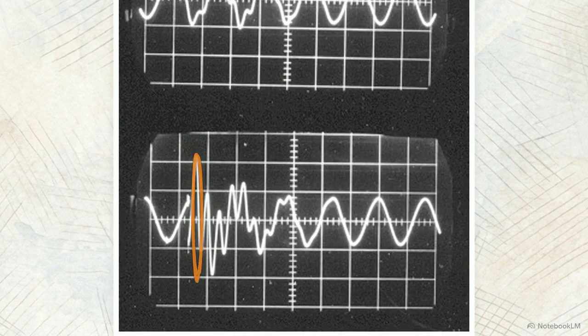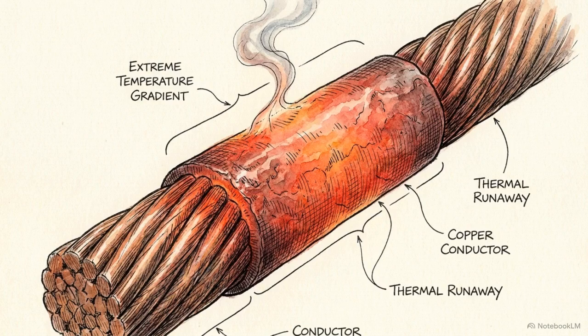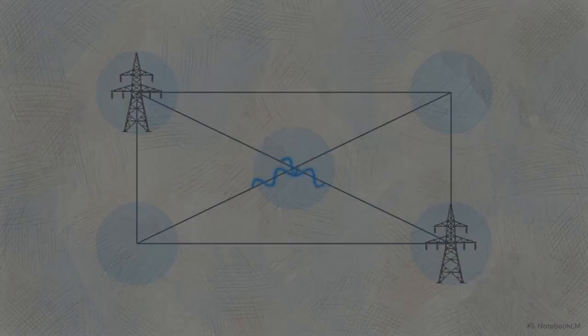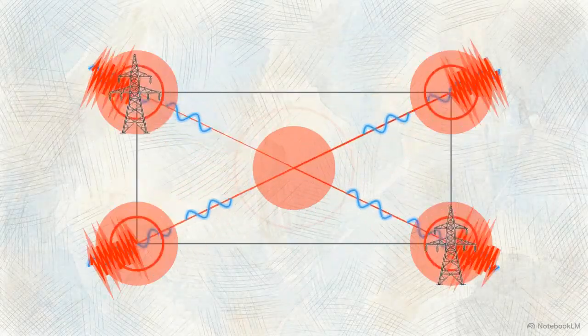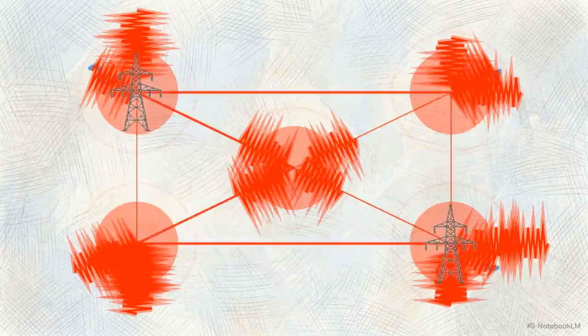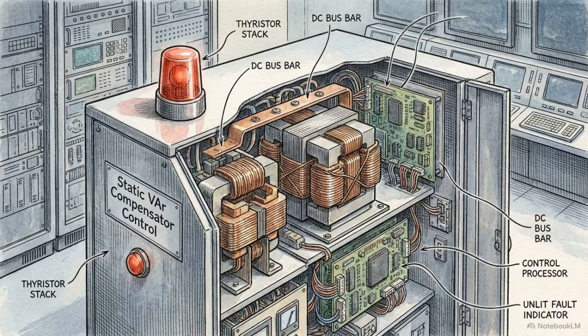Traveling onto the 735 kilovolt transmission lines, these harmonic currents created severe overvoltage peaks across the network. As these jagged waveforms pulsate through the system, they generate rapid thermal stress in the physical conductors and equipment. These distortions were now moving directly toward the SVCs, the very devices responsible for maintaining the grid stability. The geomagnetic disturbance had effectively transformed the grid's own power into a destructive frequency, heading toward the most sensitive voltage control systems in the province.